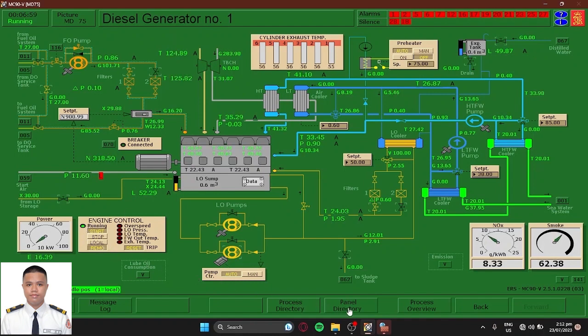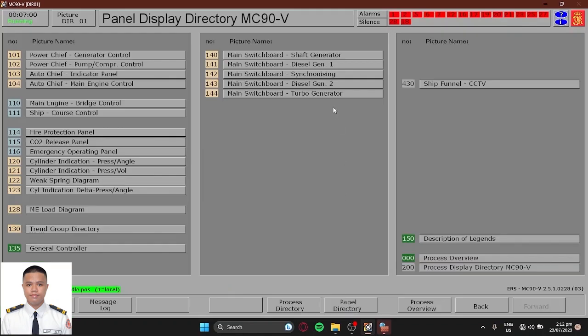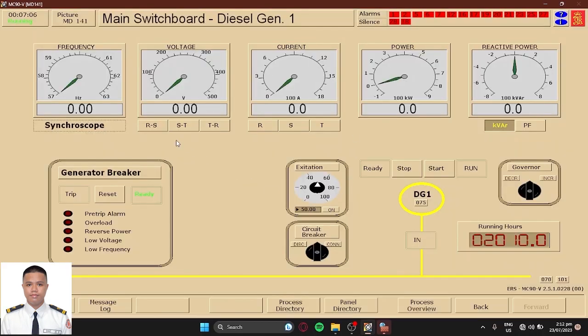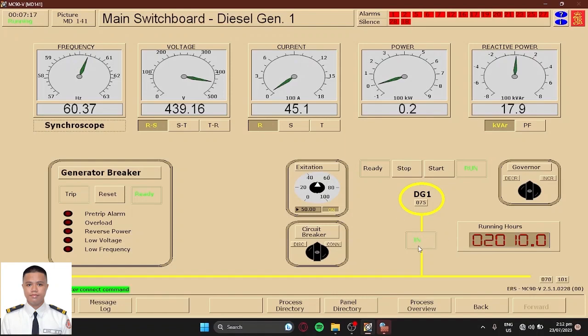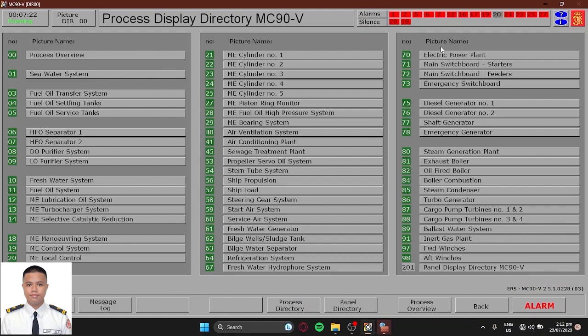Go here, panel directory. Let's connect the DG1. Go here, 141 main switchboard, diesel generator 1. What you're going to do here is select this phase, RS, press R, then excitation on. Wait for this to turn 60. There we go. And connect it. Oh, diesel generator 1 is already in. So let's go back to process directory.